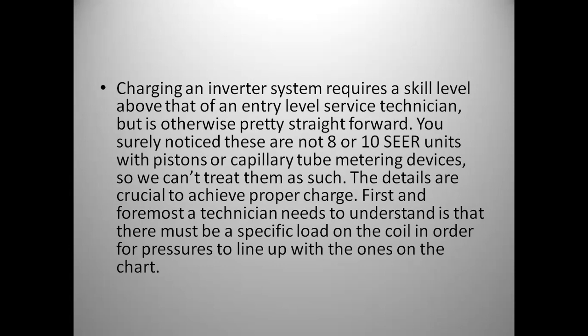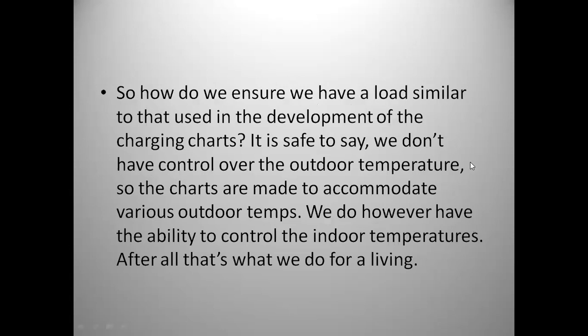First and foremost, the technician needs to understand that there must be a specific load on the indoor unit in order for pressures to line up with the chart. The pressures you see in the chart are gross pressures. Rarely will they line up identically to that, but you'll be somewhere in the ballpark depending on your outdoor temperature and the load on your indoor unit. So we'll get into some charging charts here in just a few minutes. So we ensure we have a load similar to that being used in the charging charts.